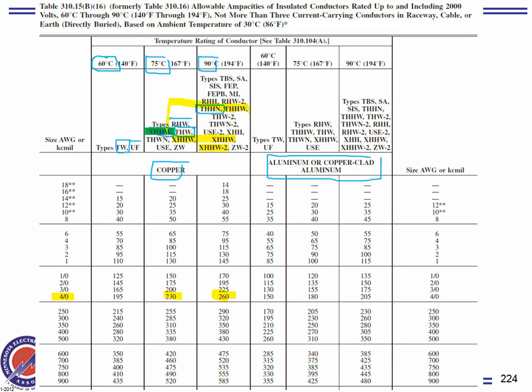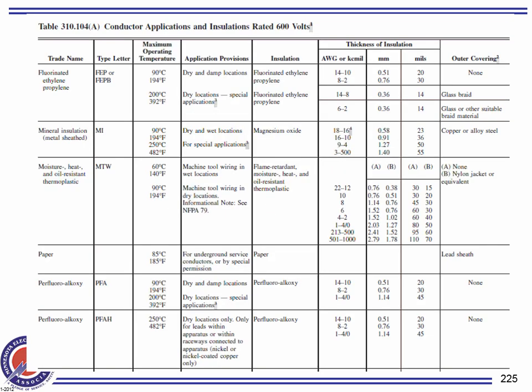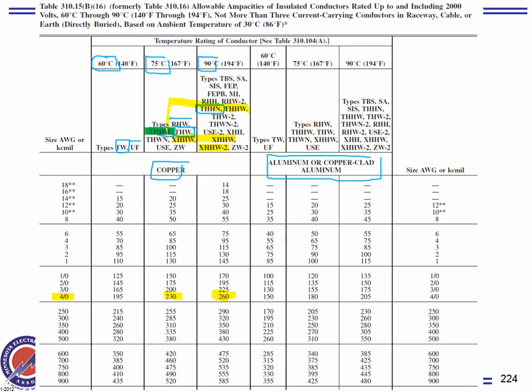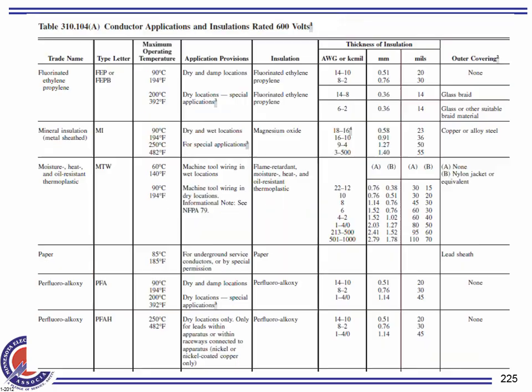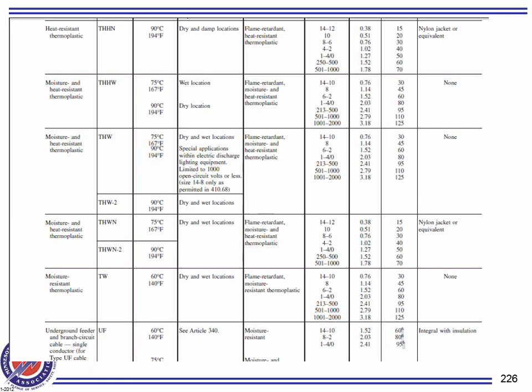Please clarify. A table. So this is the first table that you guys must make sure you know how to use. This is for an ambient temperature of 30 degrees C or 86 degrees F, and it says also for three current-carrying conductors in a raceway, cable tray, direct buried, you name it. So there's a limitation on the temperature and a limitation on the number of conductors. We'll get back to it. This table will tell you the temperature rating of the conductor.